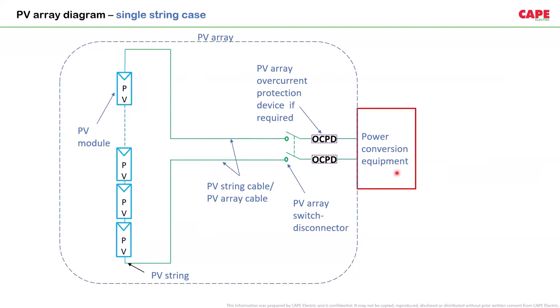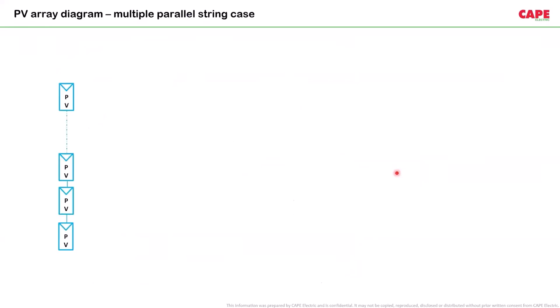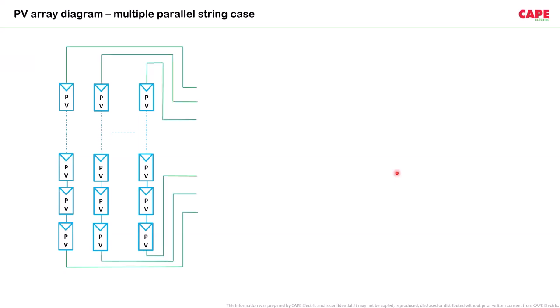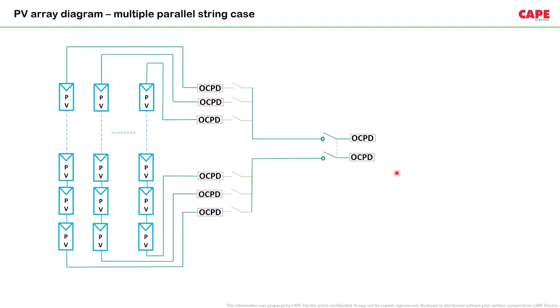voltage. One important subject which we should understand is that nowadays the solar PV DC side is operating with voltages up to 1500 volt DC allowed, but for residential purposes, anything above rooftop, the maximum allowed is 1000 volt DC. If a rooftop installation is operating with higher than 1000 volt DC, then of course the location must be limited to experts or technicians. Normal people shall not go to those areas.